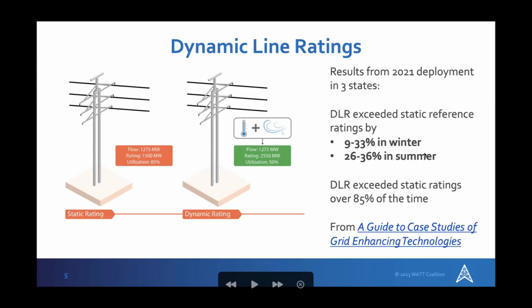In one study highlighted by a resource that the Idaho National Laboratory put together, which I really appreciate, across 3 states, dynamic line ratings exceeded the static line rating by 9 to 33% in winter and 26 to 36% in summer. That's a big increase in the capacity of those lines. It exceeded the static line rating 85% of the time, meaning 15% of the time the static line rating was either correct or actually not conservative enough.